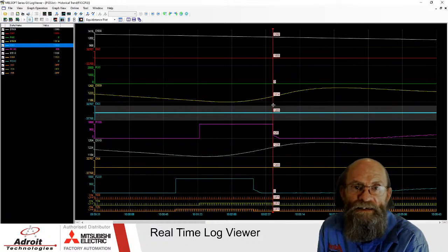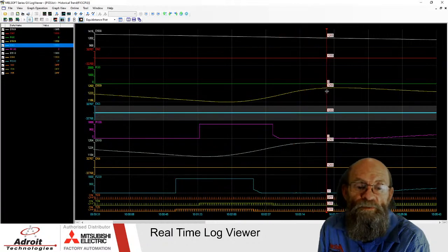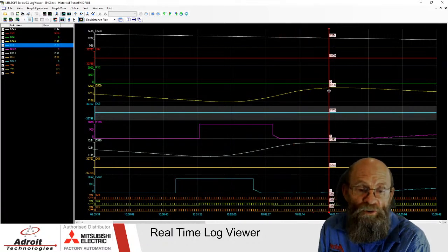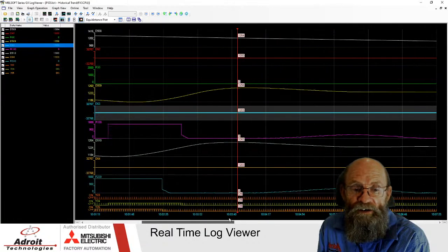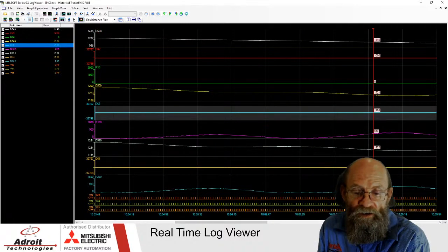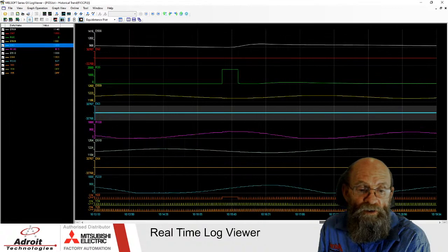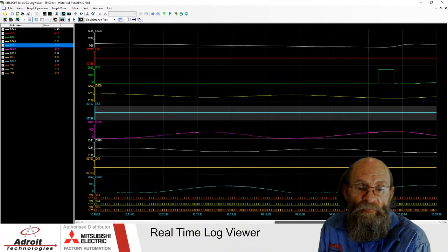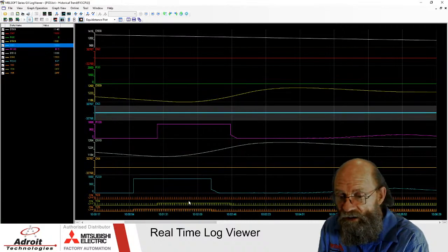But because of the size of the element, the temperature still rises further, and that's what the PID wants to learn to know about the specific element and temperature sensor, obviously, in conjunction. So then it's going to cool down to a certain point, and then the PID will take over again. I didn't record enough information here to see the full cycle, but that's what you would see. Okay, so your temperature will rise up, your element will switch according to certain time intervals.